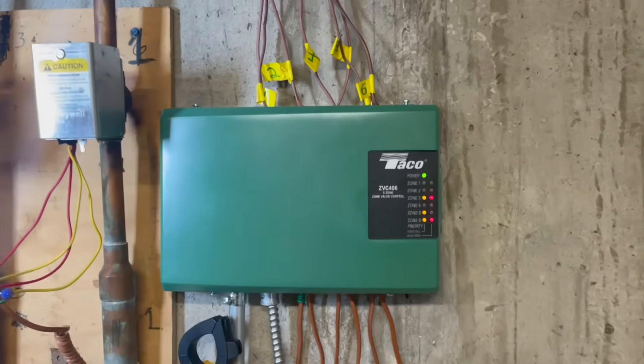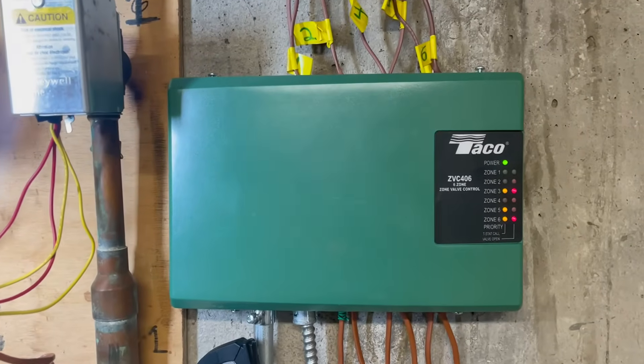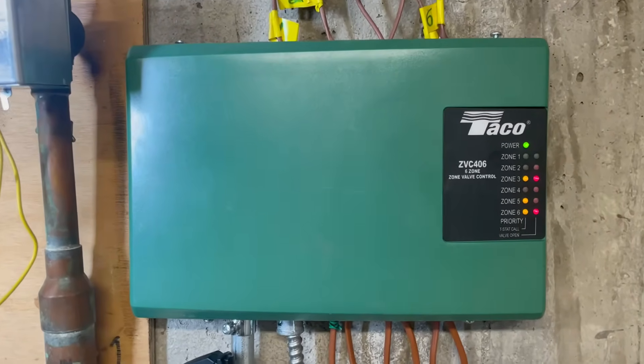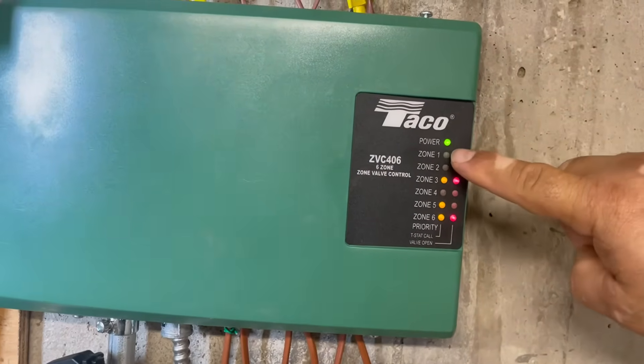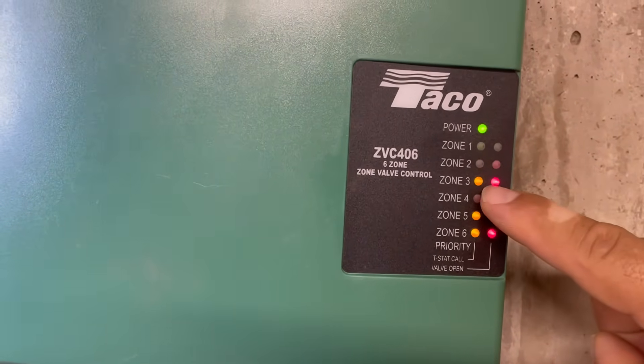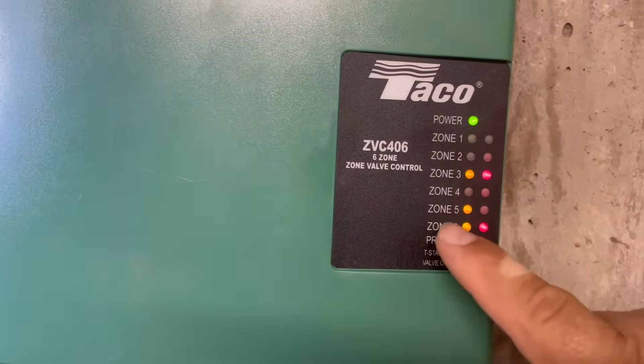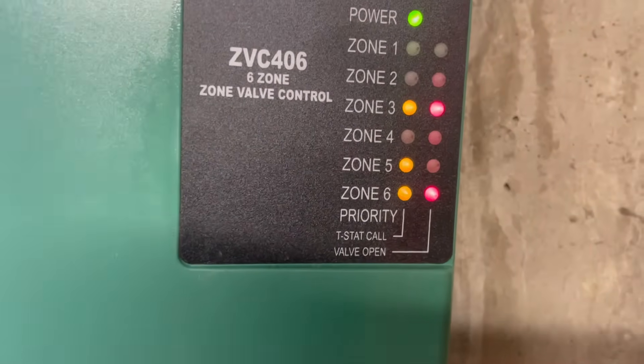Hello guys. I'm in a service call and this is the Taco I just installed in the last video. So we have power. Apartment 1 and 2 are not calling. Apartment 3 is calling and the pump is on. We have a problem with Apartment 5, Zone 5.